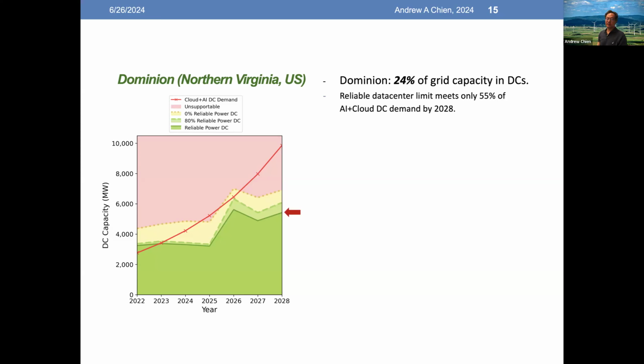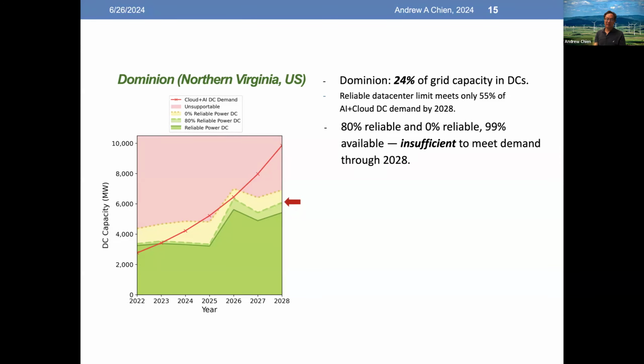If you use this projection, using the reliable data center limit, the planned capacity of the Dominion grid will meet only 55% of the AI and cloud data center demand by 2028. So they're in the process of radically revising their plans and their estimates up and up and up to try and catch up to this exponential because they were not planning on it. If you look at the 80% reliable and 0% reliable, they're both grossly insufficient to meet the demand as well.